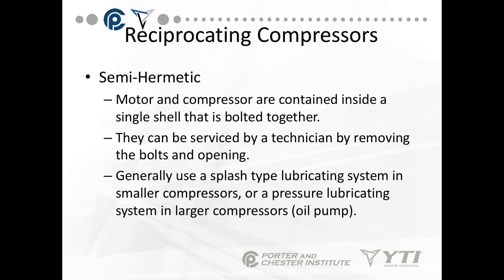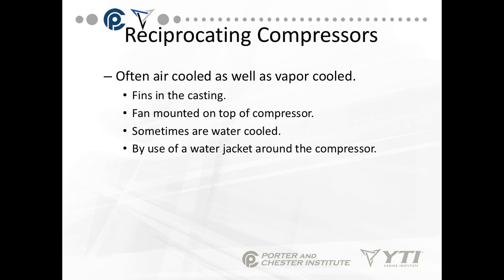Semi-hermetic is just a step away from that — a more expensive system. The motor and compressor are contained inside a single shell that is bolted together. You can service the inside components by removing the bolts after recovering all the refrigerant, then opening it up. Generally they use a splash-type lubricating system in smaller compressors or a pressure lubricating system in larger compressors using an oil pump. They're air-cooled as well as vapor-cooled — fins on the casting allow increased surface area. A fan is mounted on top of the compressor. Occasionally you'll see some in hotter environments that are water-cooled, using a water jacket with tubes where water circulates.